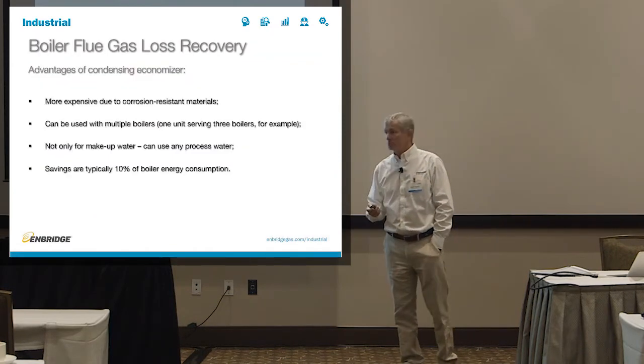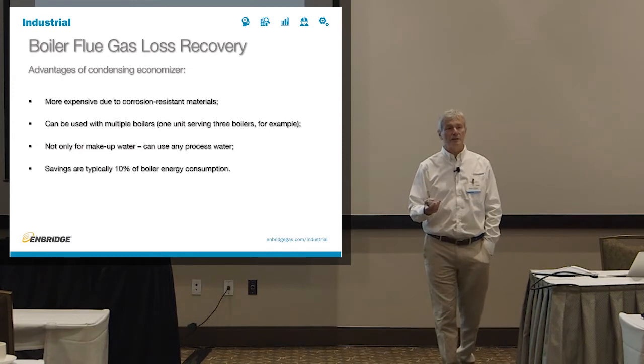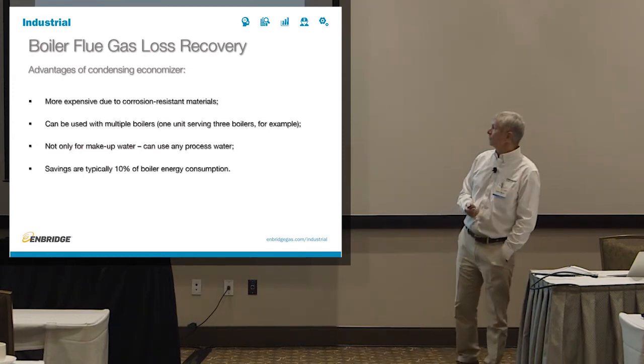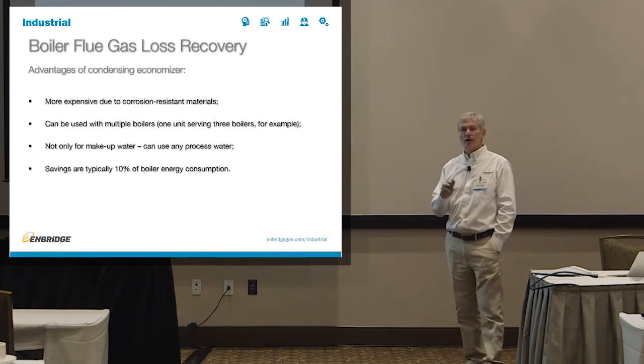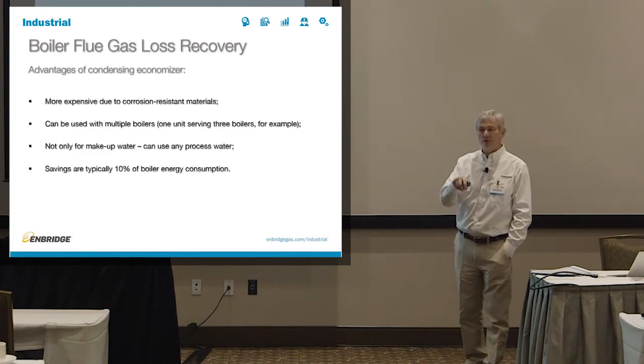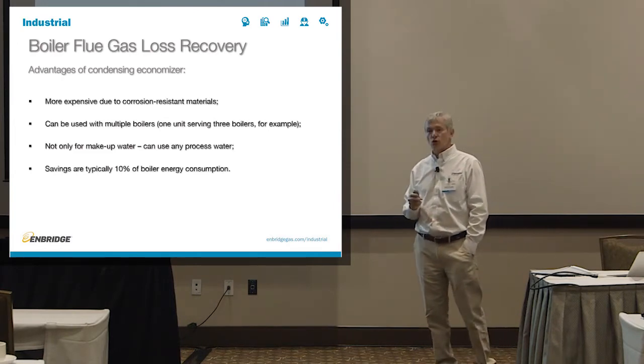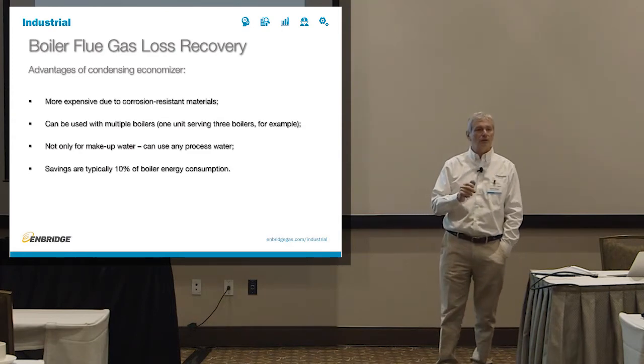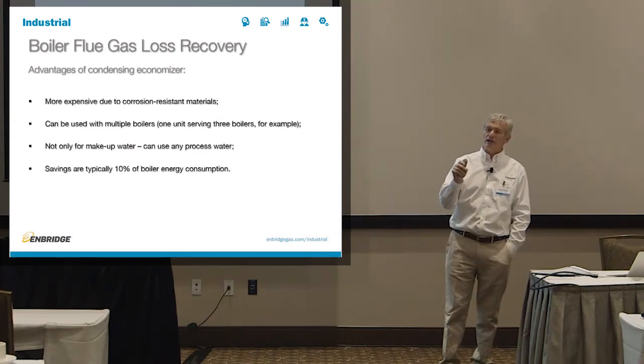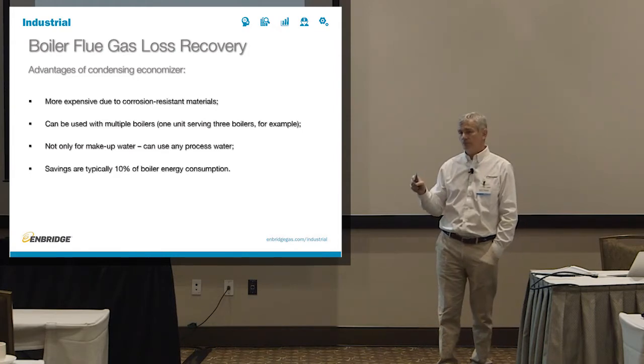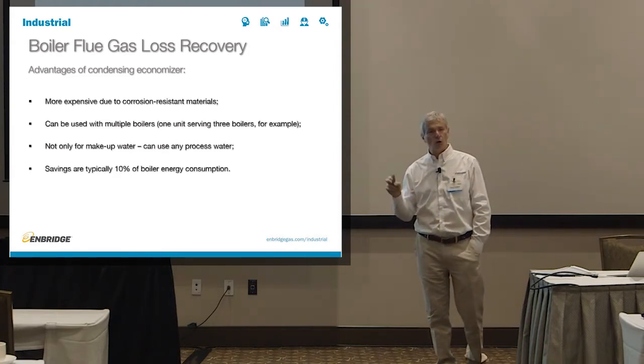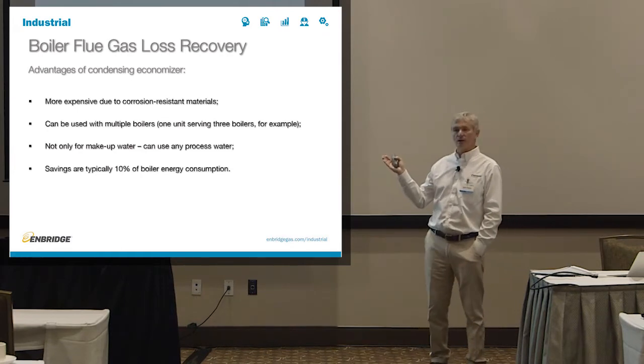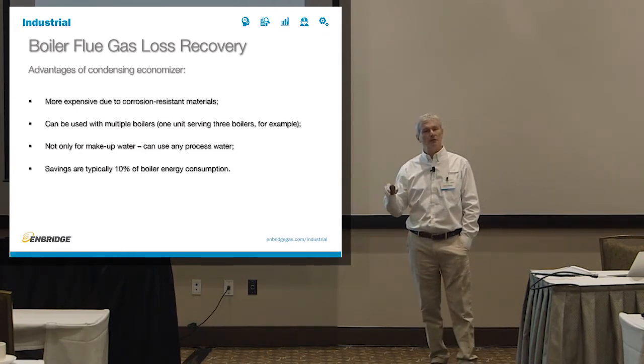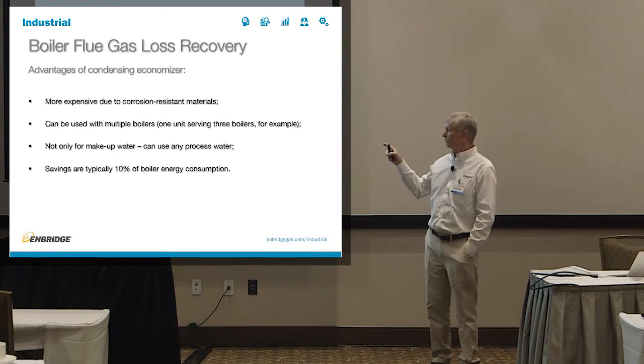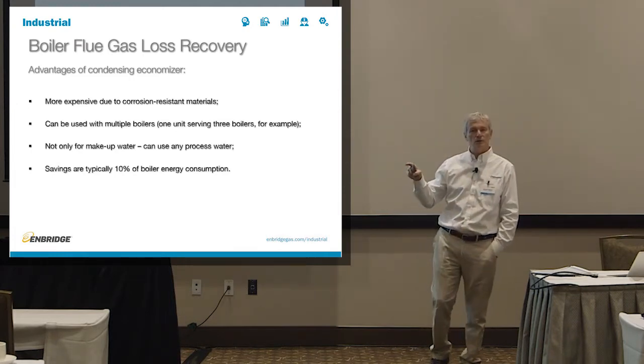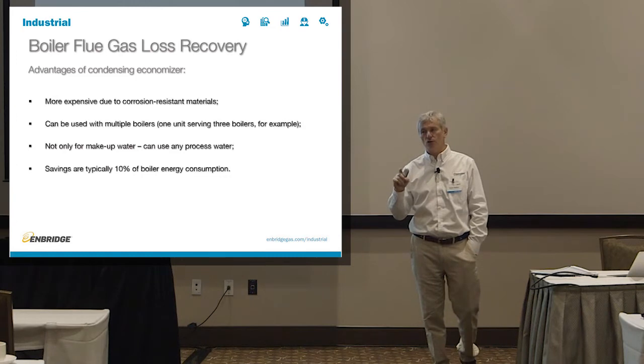So condensing economizers are more expensive because you have corrosion-resistant materials. They can be used with multiple boilers, however, so you don't have to have three at $25,000. You can just buy one. It's not only for the feed water. It's good for the makeup water, and it's good for the process water. And savings are typically, on their own, about 10% of the boiler energy consumption if you add it to the existing feed water system. So if you have a feed water economizer and you put in a condensing economizer, you will save about 10% of the energy going into the steam boiler.